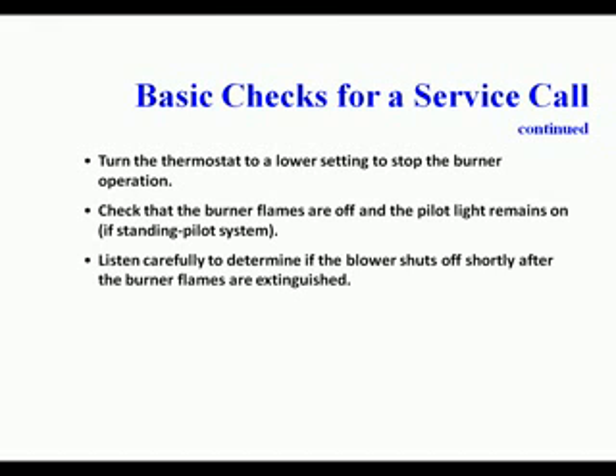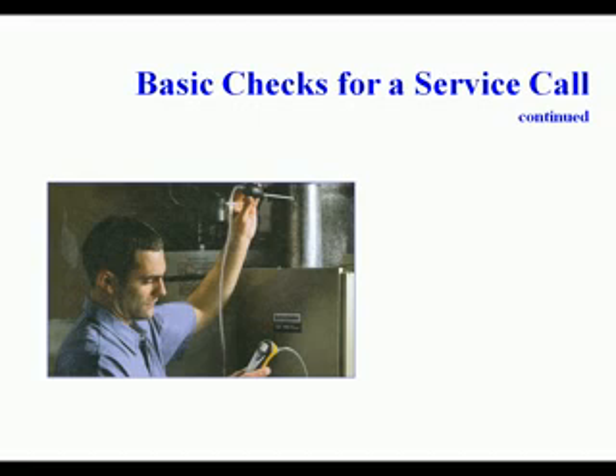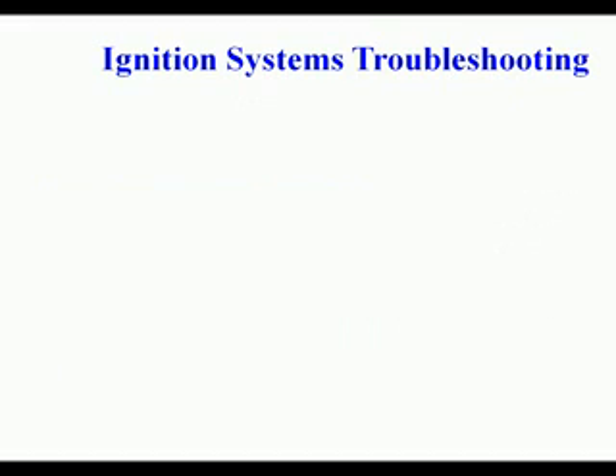Start the furnace operation by placing the thermostat in the heat demand setting. Observe the burner startup and during operation. Observe the fan motor startup. Allow the furnace to cycle for about 10 minutes. Check the airflow through the room registers. Turn the thermostat to a lower setting to stop the burner operation, and check that the burner flames are off and the pilot remains on if it's a standing pilot system. Listen carefully to determine if the blower shuts off shortly after the burner flames are extinguished. Check exhaust for carbon monoxide levels, and always refer to the manufacturer's manuals.